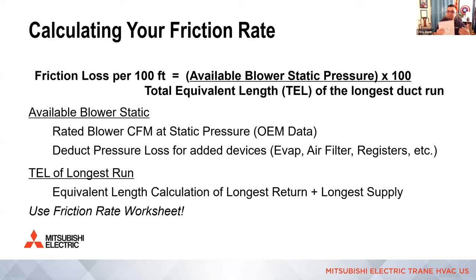What I want to explain to you guys today is that may work in 1 in 100 houses. When you change the air handler, the friction rate changes, and that's because your available blower static changes. And it's possible when you make duct transitions that the total equivalent length of the longest duct run changes. So when you do this, this is not static pressure. This is friction loss that you're setting on your duct calculator per 100 feet.